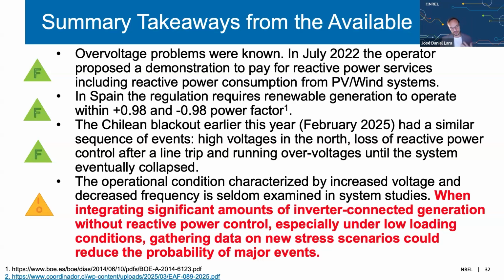The situation we observe is that the rules of the grid code to integrate inverter-based generation without reactive power control are probably fine at, say, 20-30% penetration, but now reaching 70% penetration with the same rules, it stands to reason that the system started to suffer from conditions that made it unstable.